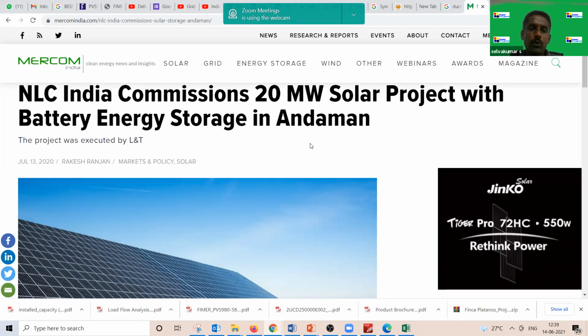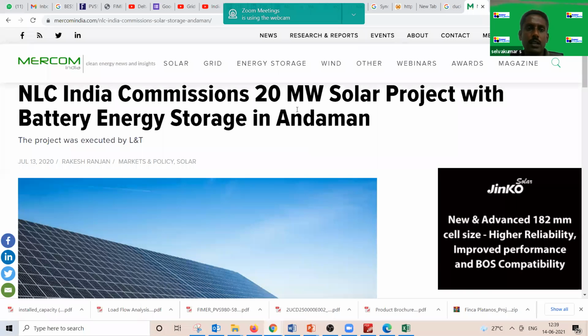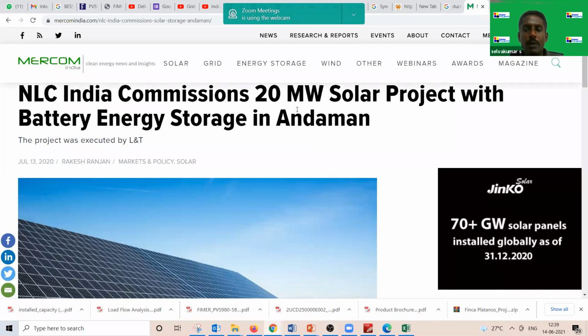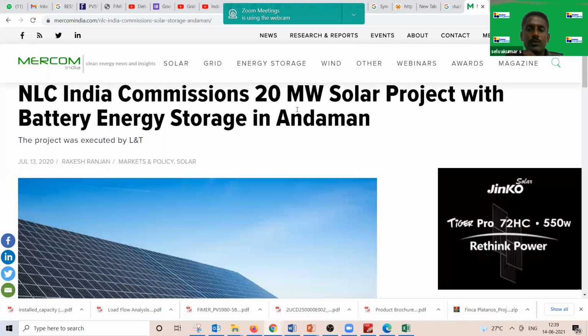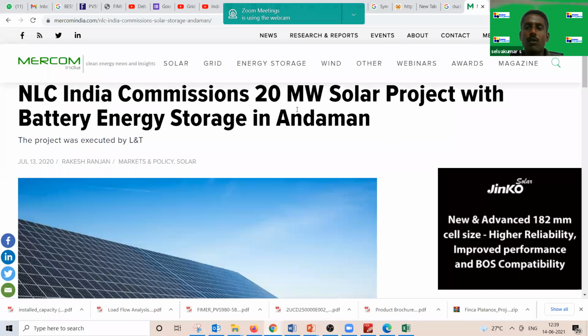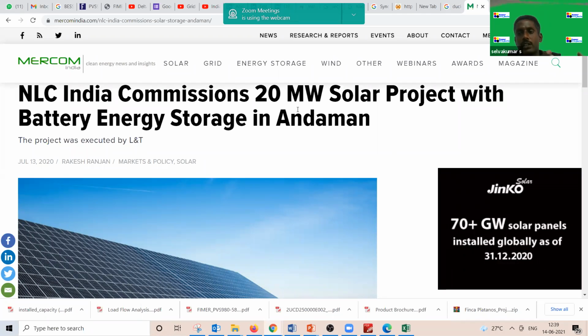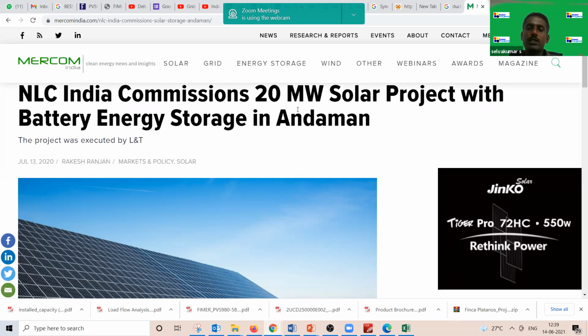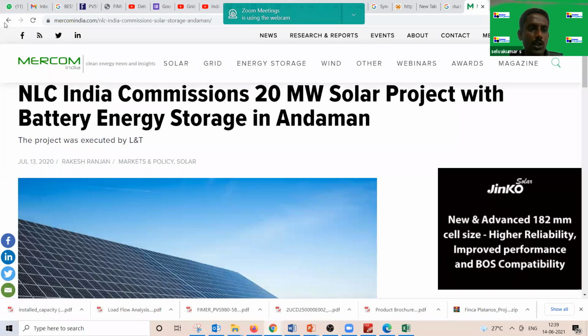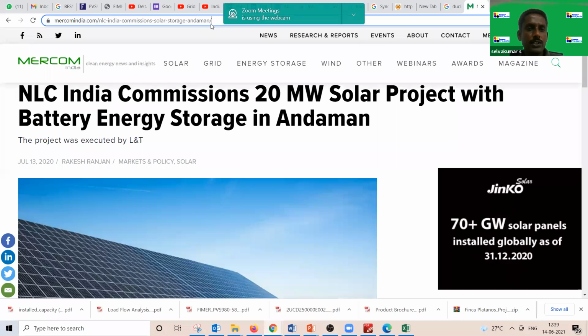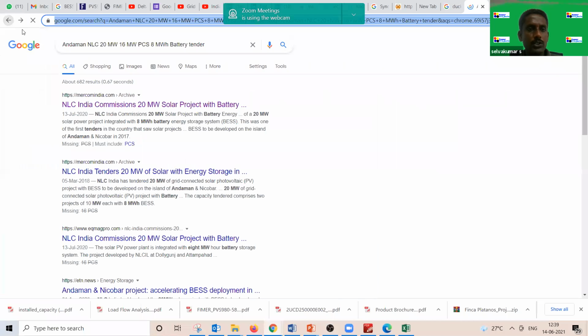So they decided to go with 20 megawatt solar plus 8 megawatt hour battery energy storage with 16 megawatt PCS, which does the job of shifting the daytime generation to meet the evening demand from 6 to 10. What I did was simply Google the terms Andaman NLC 20 megawatt, 16 megawatt PCS, 8 megawatt hour battery energy storage tender, and you'll get this tender documentation showing how to size all these things.